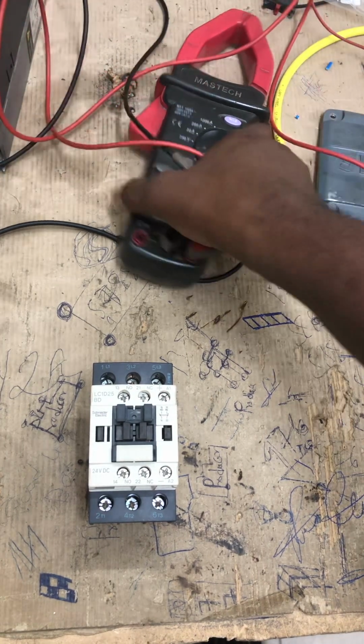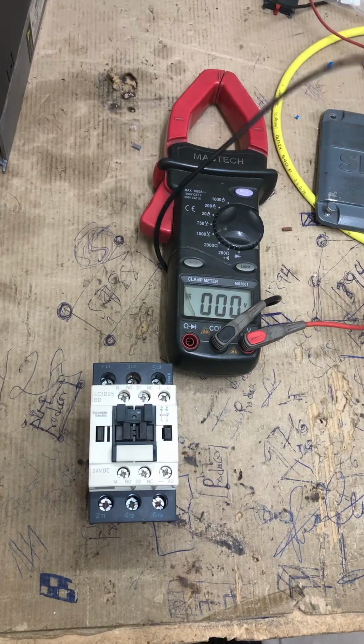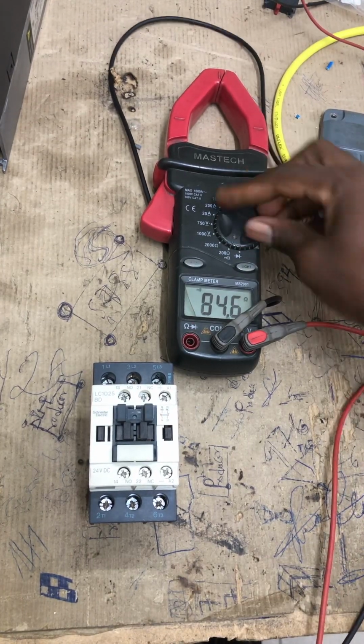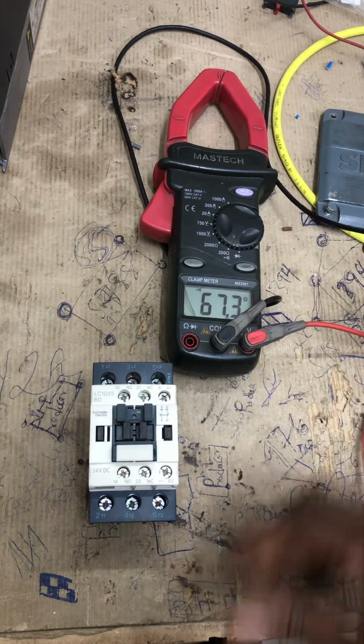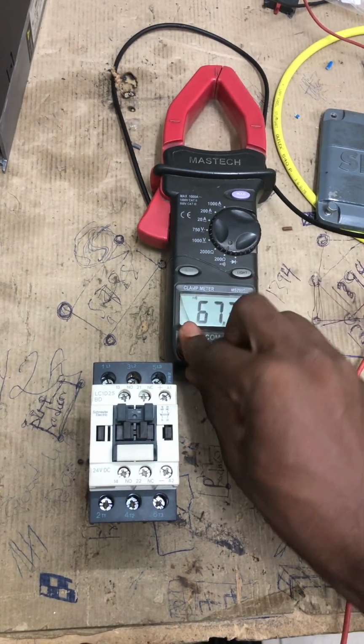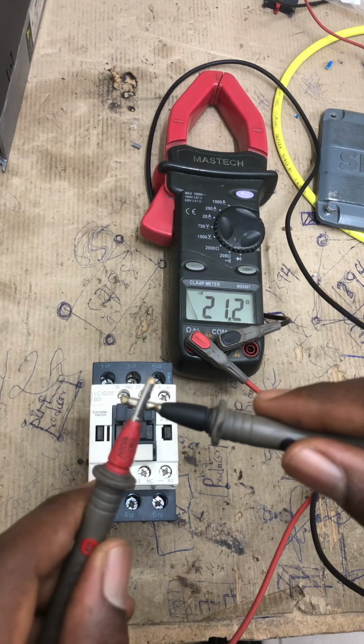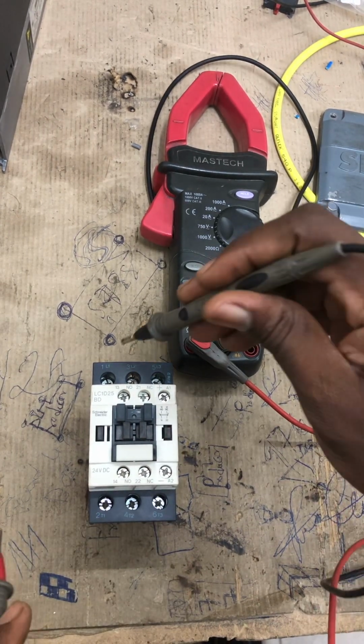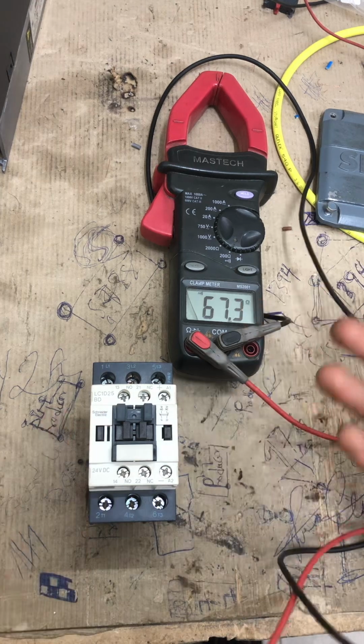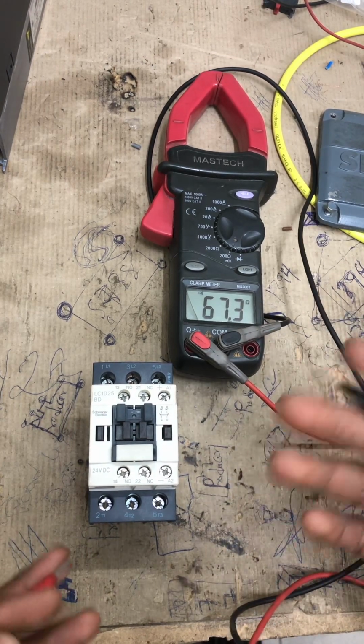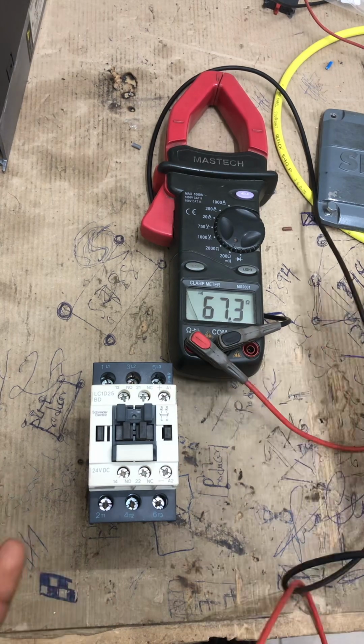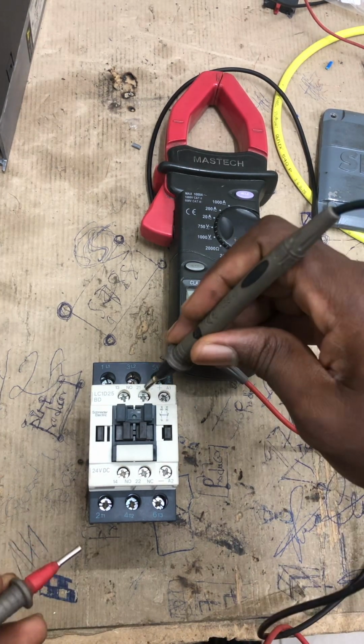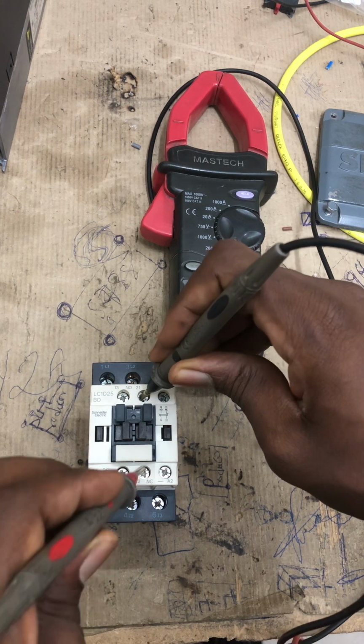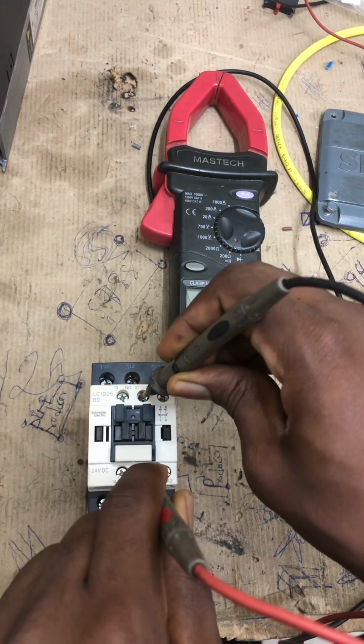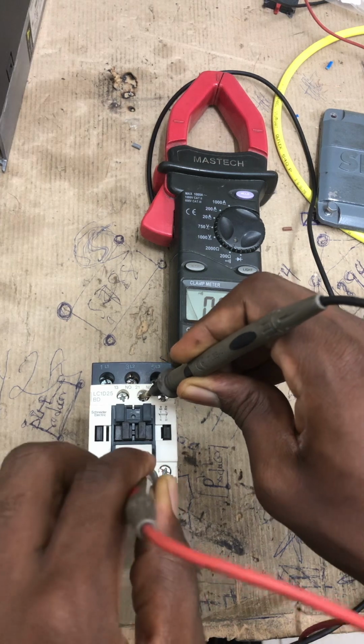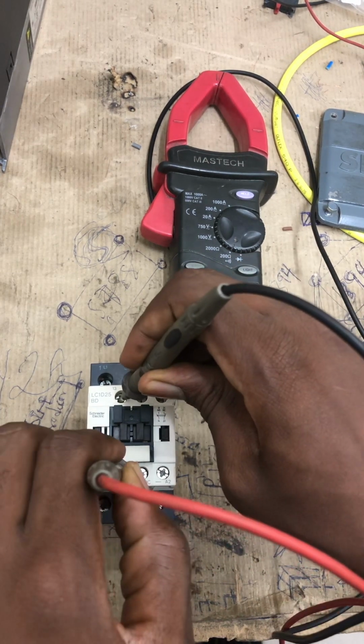To do that, you take your meter, switch it on, select your ohms reading. We'll be using the beep sound. Make sure your probe is inserted in the ohm column. Test your probe. You are not supposed to get any beeping in the normally open sections, and we are supposed to get a beep sound in the normally closed section. We have only one normally closed section, that's the 21, 22 contact. We are supposed to get a beep sound. For the rest, we are not supposed to get any beep sound.